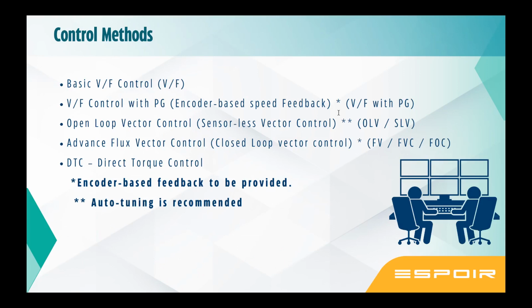Now, for example, if you wanted to do a feedback to the V by F with PG, second option, your drive also should have a facility to read the encoder feedback. Generally, standard drives don't come with that option. You need to buy an encoder feedback card. Closed loop function or advanced closed loop vector control, again, you need to buy the encoder feedback card. You need to have an encoder. What type of encoder? There are 6 or 7 different types of encoder based on its output. You need to analyze that and then buy a card accordingly. You get an encoder card and choose an encoder according to that.